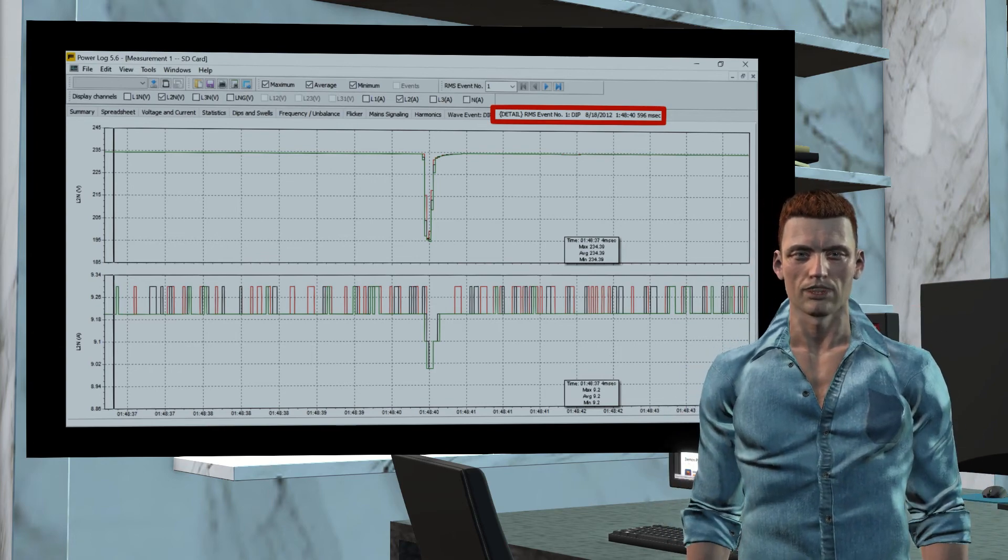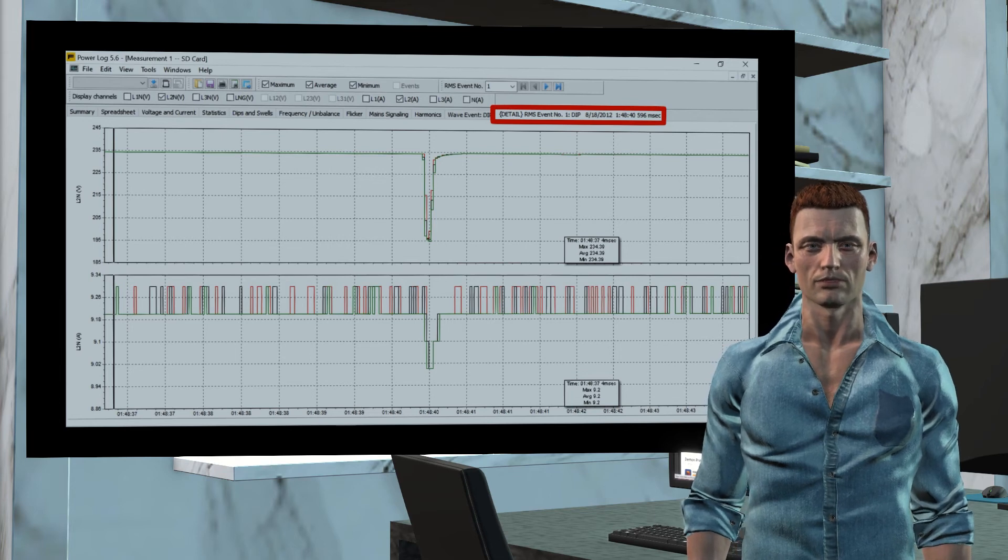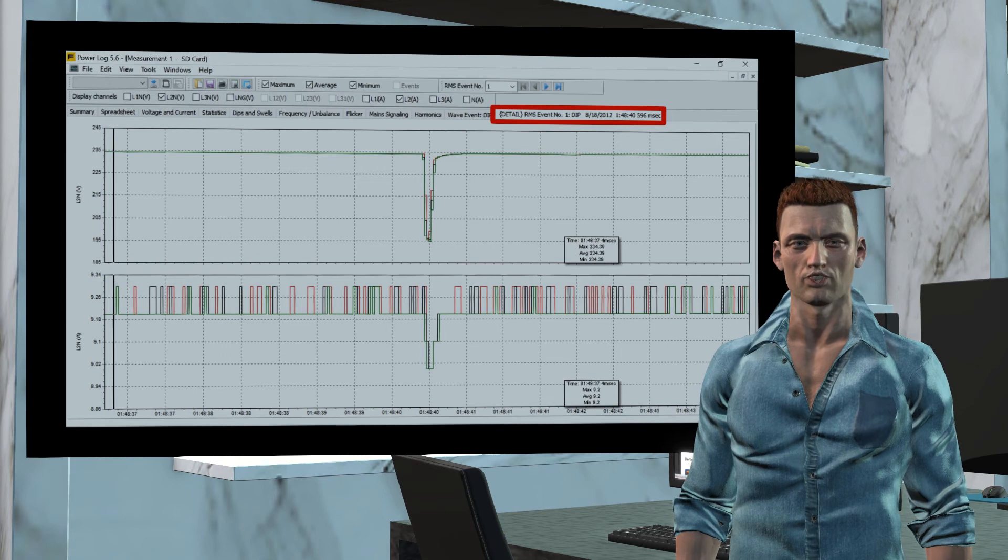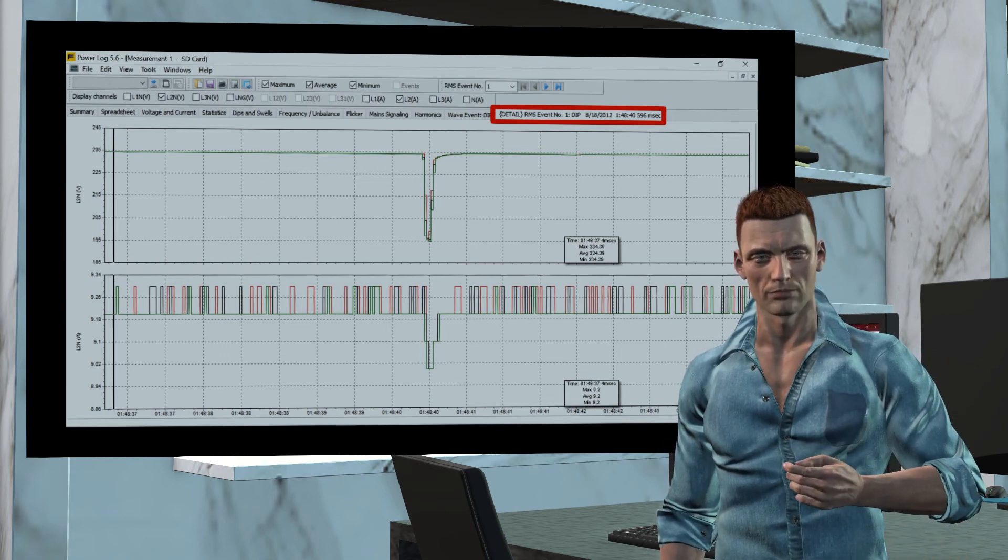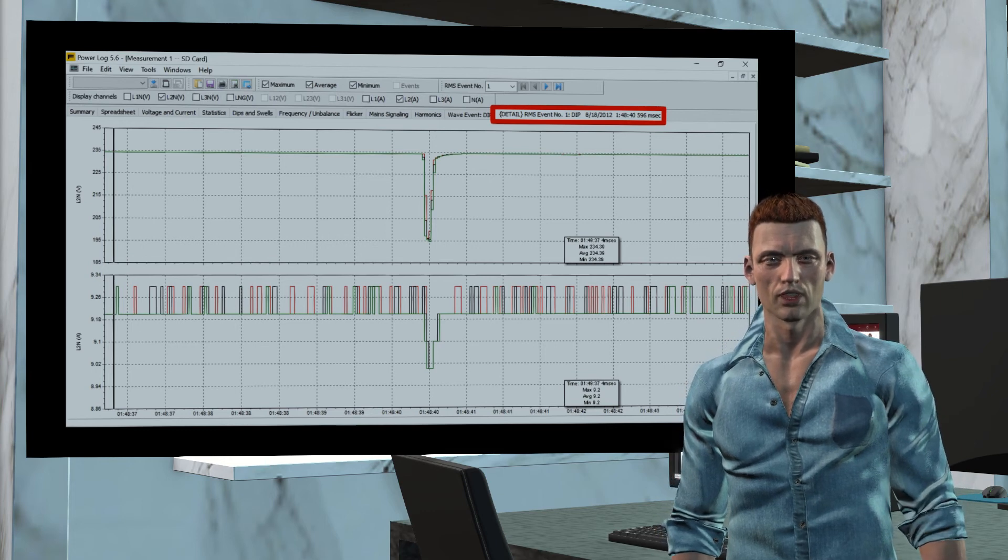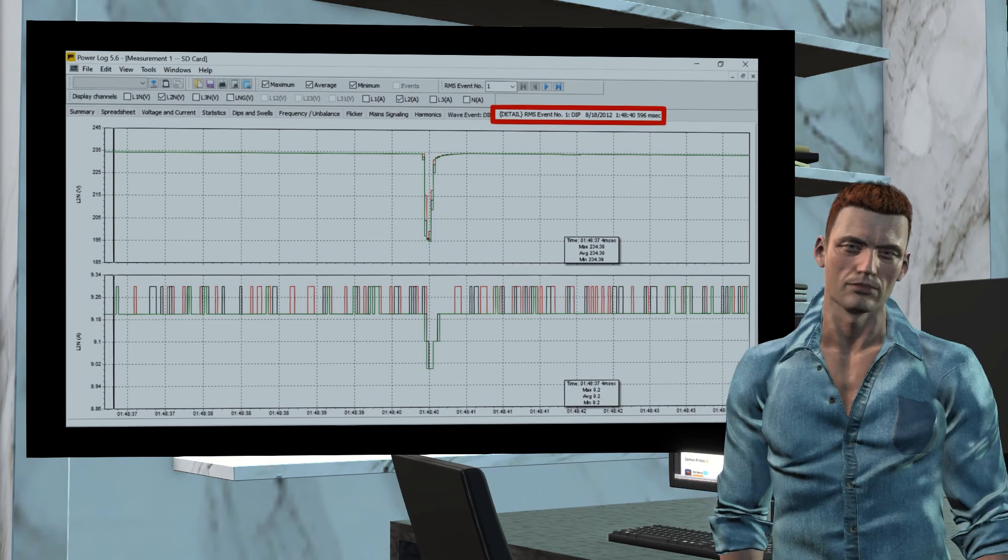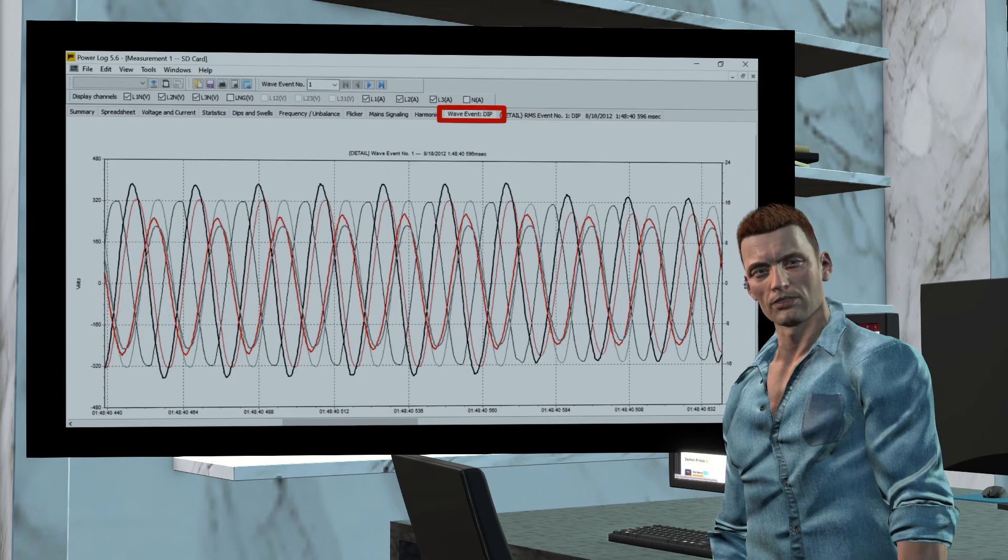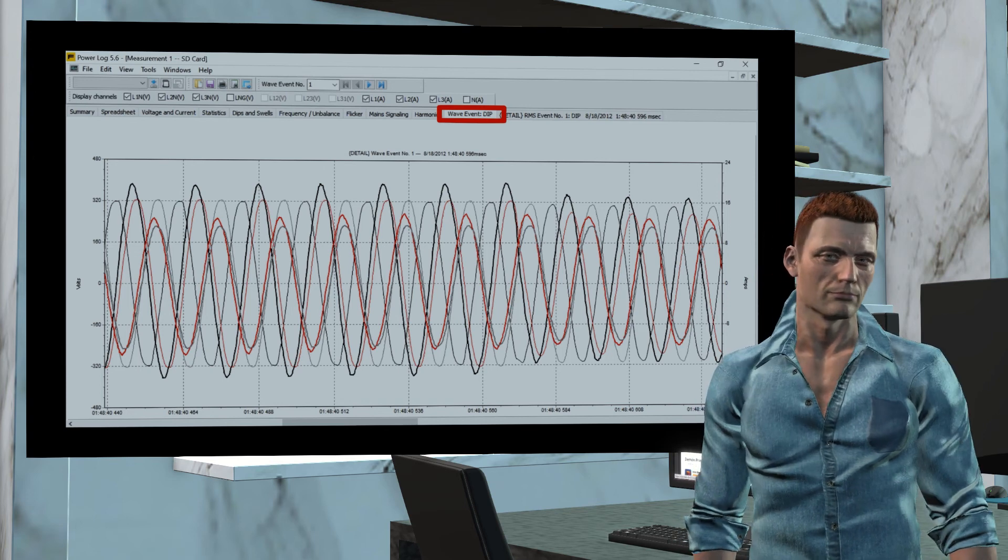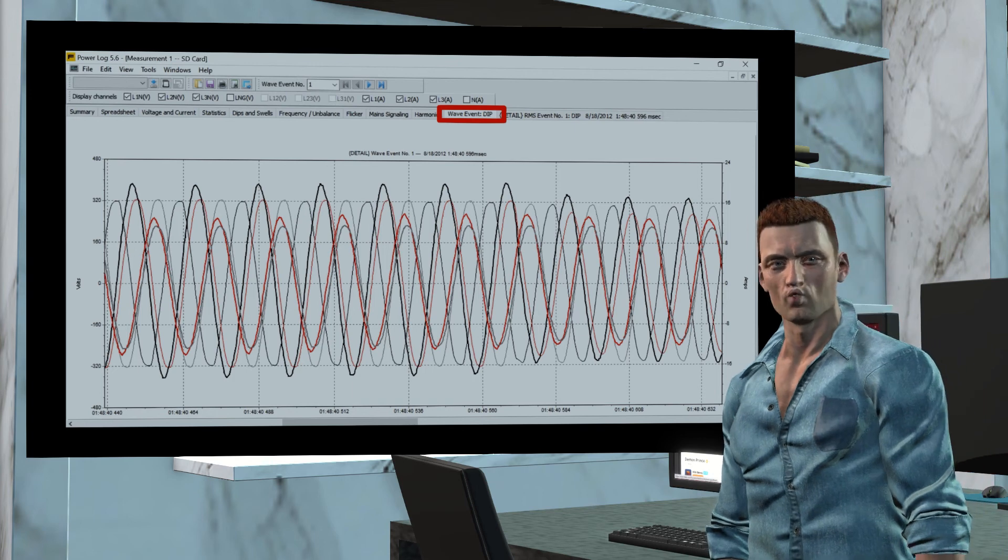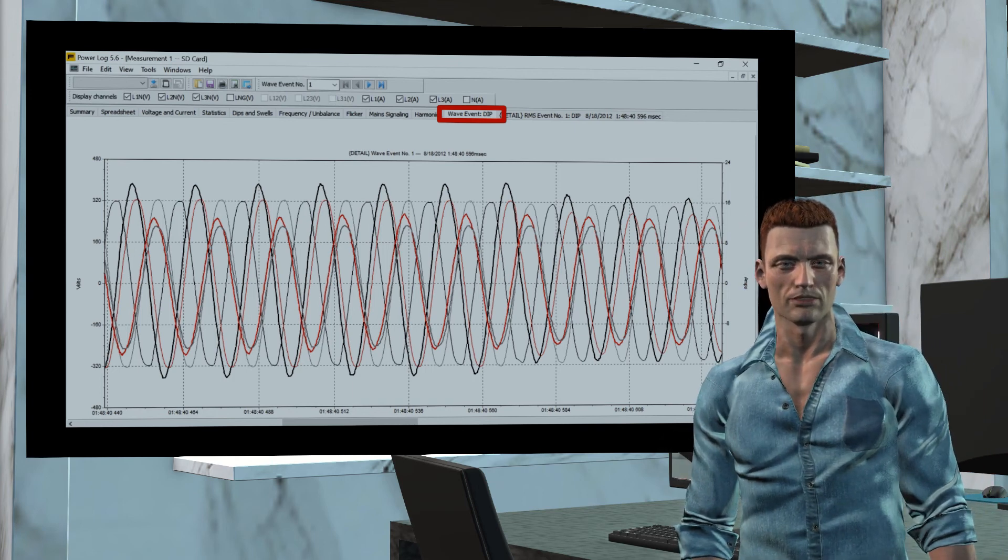However, if the Fluke 430 analyzer detects an event, and in this case we must remember that the analyzer uses the RMS values of half a cycle, the Fluke 430 analyzer will be able to display trend graphs for each event with a much higher temporal resolution, down to 25 milliseconds between consecutive points. In case of an event, the 430 analyzer can also save the waveforms associated with that event, and in this case the time between two consecutive points in the waveform will be less than a millisecond, providing you an incredible resolution.